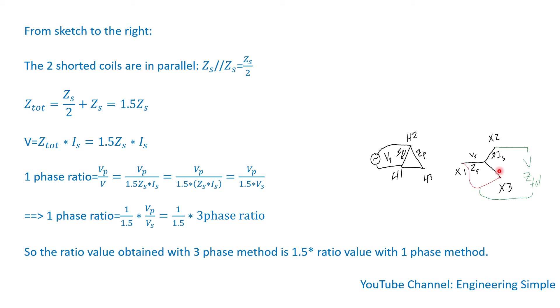In summary: if you cannot access the neutral of the Y winding, you can measure the voltage ratio using the single-phase method. Apply voltage to one winding on the delta side and one winding on the Y side, with the untested windings' terminals shorted. To get the equivalent three-phase voltage ratio, simply take 1.5 times whatever voltage ratio value you obtained from the single-phase measurement.